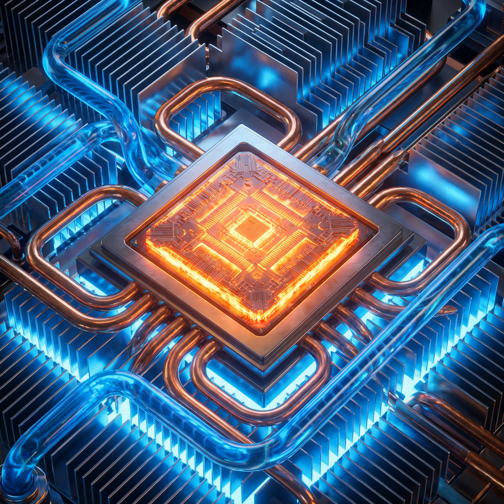And the environment is different too, right? In a data center, they are not just cooling one computer, they are cooling the whole room. Yes. They use what we call hot aisle and cold aisle containment. The front of the server racks all face each other in the cold aisle, where cold air is pumped up through the floor.